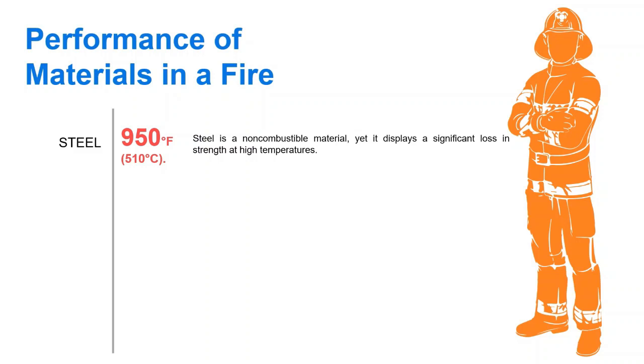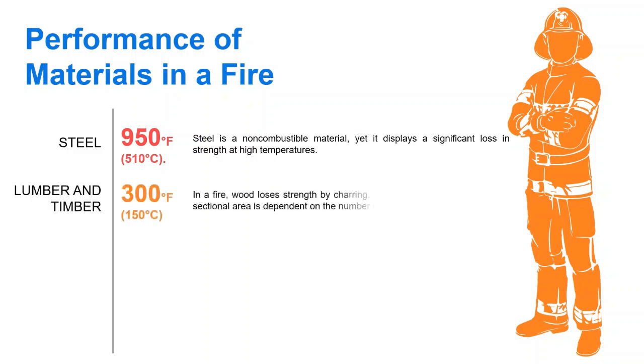As a result, structural steel is typically protected from fire by an insulating layer of fire-resisting material. A fire-resisting material limits the temperature rise of steel in a fire to keep it from losing strength. Stronger materials such as concrete or masonry may also contribute to the load carrying capacity of the assembly, thus extending in some cases the fire endurance.